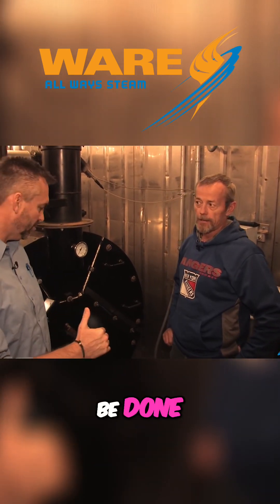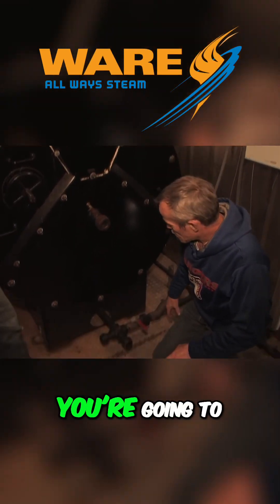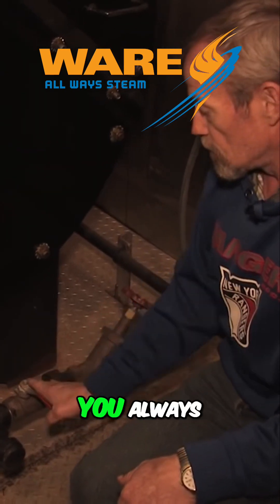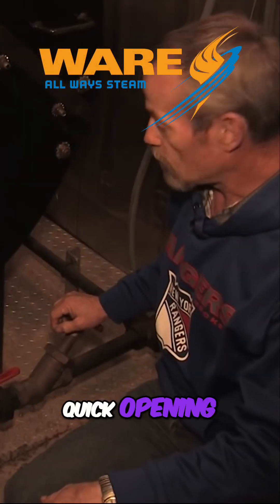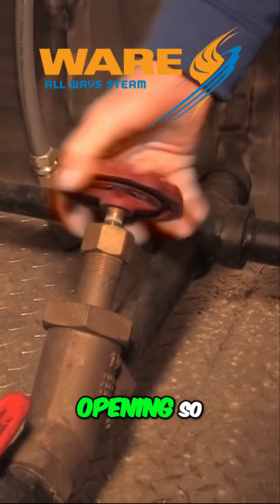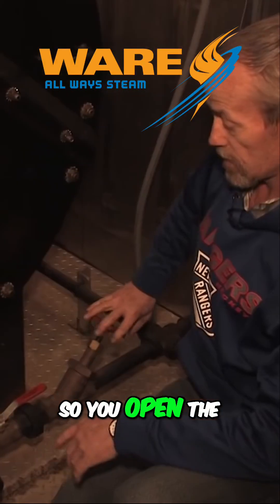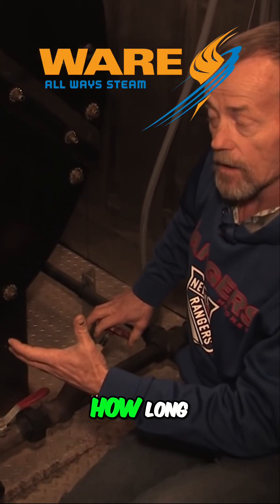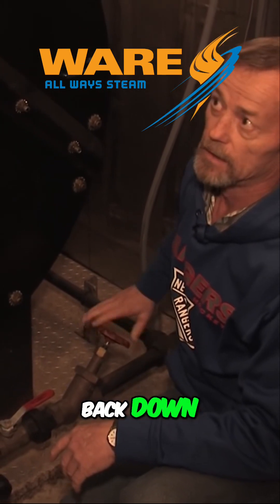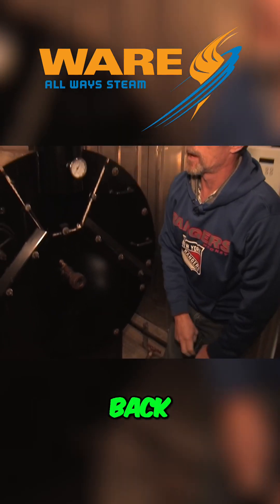This is a daily thing that should be done. On the main blowdown, you're going to have a quick opening and a slow opening on most boilers. You always open the quick opening first — it's just a backup. You want to open the slow opening so that you don't stress the pipes and blow them off. Open the valve all the way, and depending on how long your chemical guy tells you to blow it, then you close it back down. Typically it's going to be a 10-second blow. Then shut your secondary valve back off.